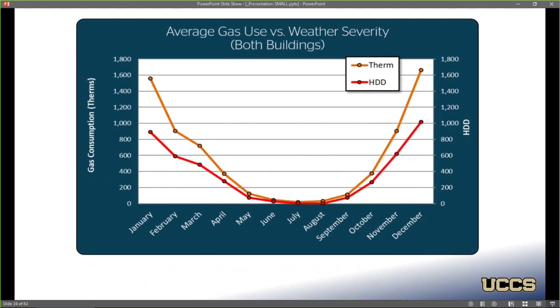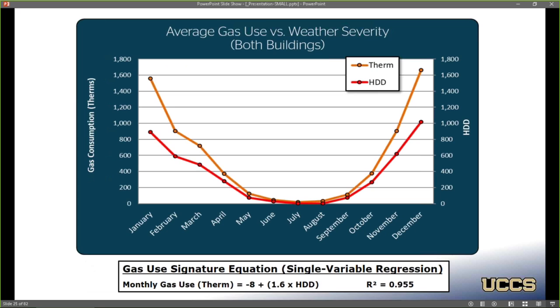On the gas side, here you have gas use plotted against the heating degree days, and you can see a very, very clear correlation between rising heating degree days and rising gas use. And the equation here was, again, generated with a fairly high R squared. You might notice that the constant is actually negative, which doesn't really make any sense, but I just take that to mean that it's very near zero. The only gas load you'd expect when it's warm out is the lab domestic hot water heater, and that load is going to be very, very small.